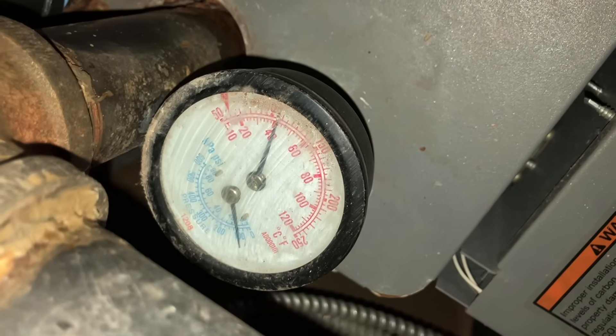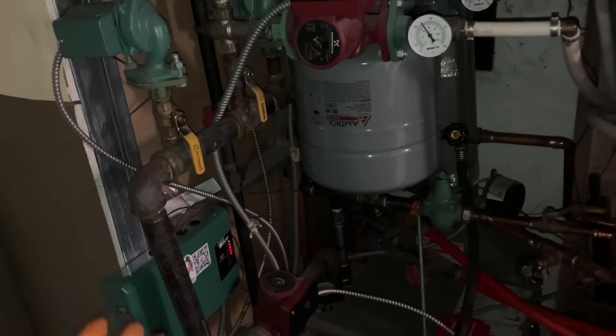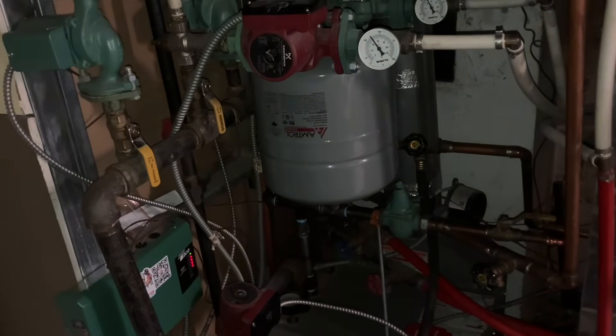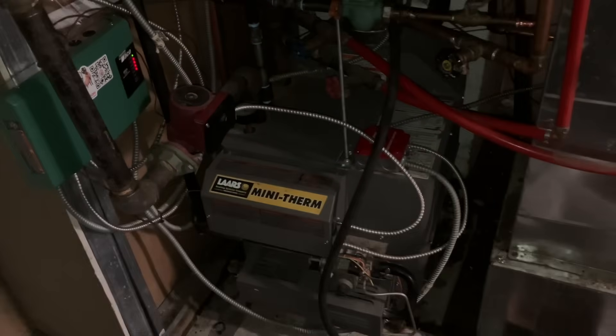Let's close our fill valve, close our drain, open up the isolation valve that was preventing water. I'm going back to the boiler. Temperature cooled off drastically. This is getting hot again — I feel it. Hopefully that one gets hot as well. There's no air removal anywhere — no means to remove air. This is like a losing battle. Idiots who installed this.